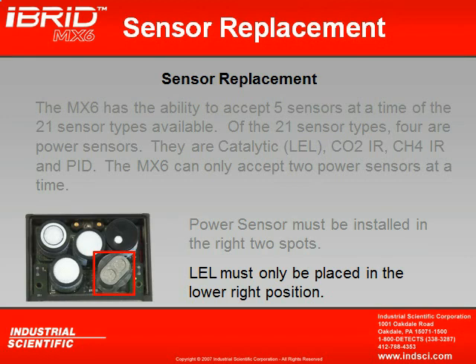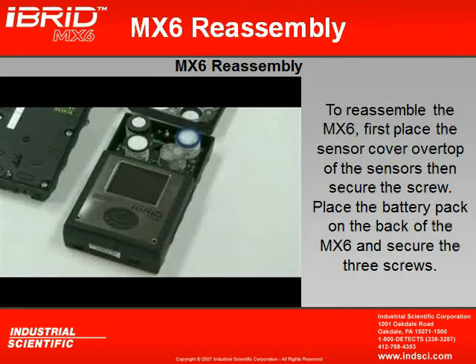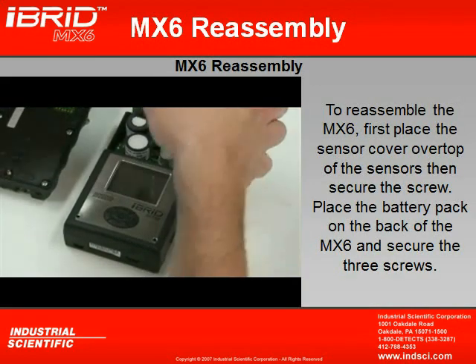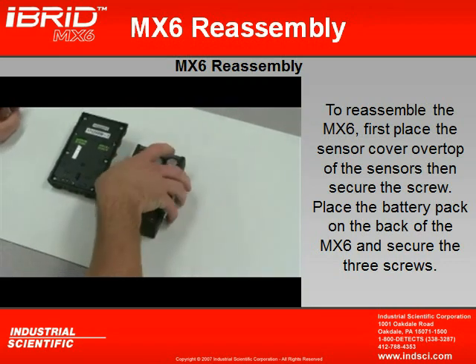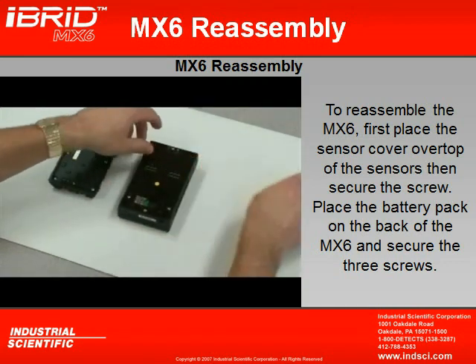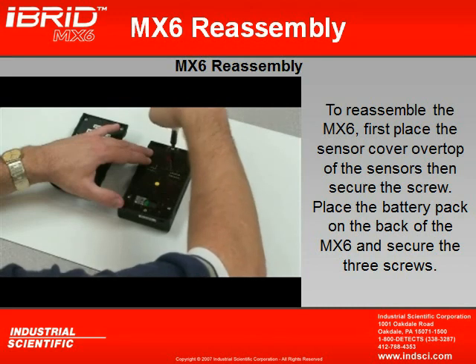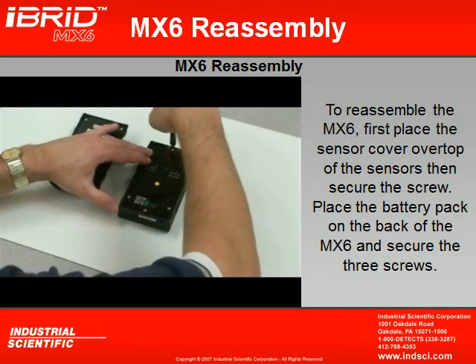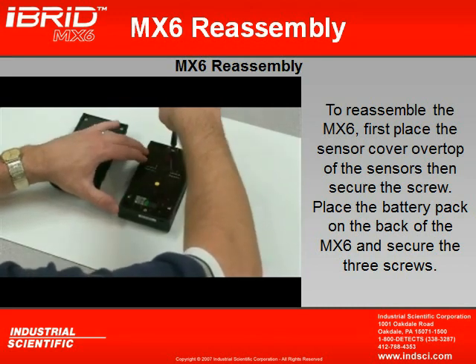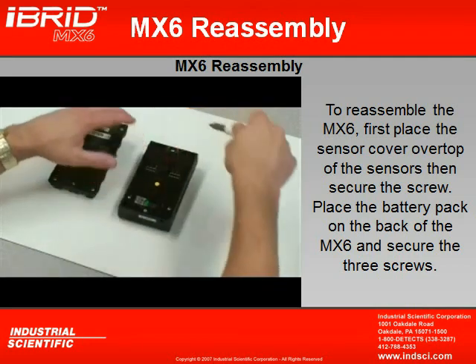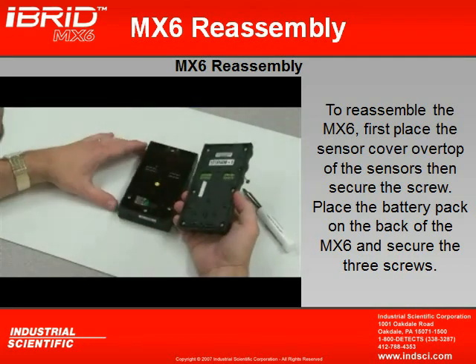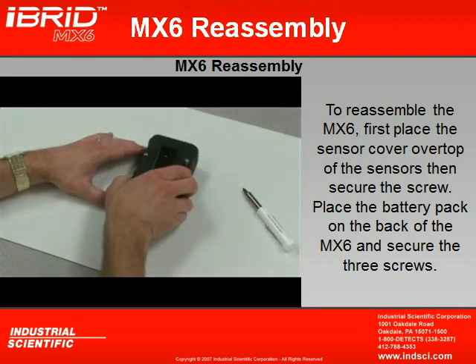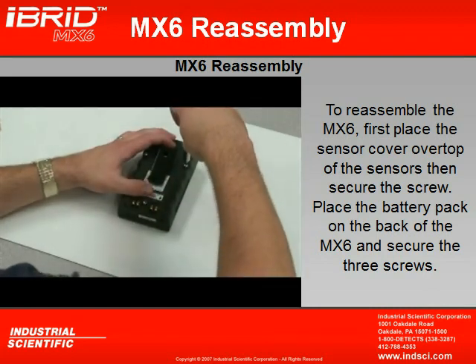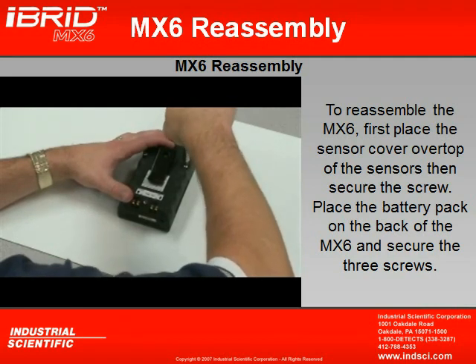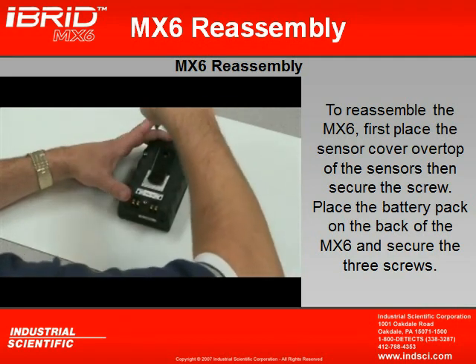Okay, so let's look at reassembling the MX6. First we put our sensor cover on. Once we have the sensor cover on, we can now tighten up our Phillips head screw. Once that screw is fully tightened and in place, and not over tightened, just to the point where it's snug, we can then put the battery pack back on. Once again, we've got the 3 captive Phillips head screws, and we just tighten those until they're snug. We don't want to over tighten these. And once they're all in place and fully tightened, the instrument will be fully reassembled.